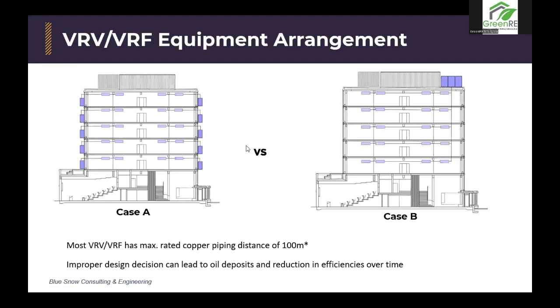So what happens if you don't do it? Because in our experience, we've seen, even in Malaysia, oftentimes from the designer's perspective, if they're using a VRV, they just say, okay, this indoor unit of this cooling capacity sits here. The copper pipes just go straight and just go out to the outdoor unit. They don't really size it from that point. They leave it to the contractor. And the contractor, most of them are not really that skilled. So they just go by the same methodology that they would often use in split unit installation. They will use the same approach for your VRV. And that will lead to certain issues.